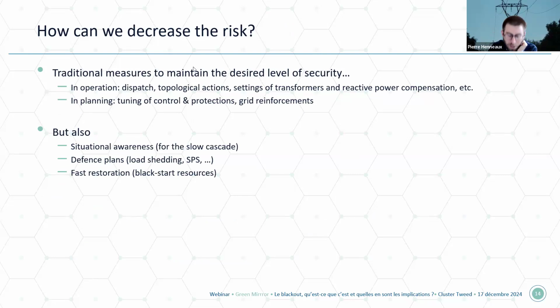We can have the analogy with the measures to ensure deterministic N-1 security. So the traditional measures to maintain the desired level of security are, in operation, the dispatch and the use of topological actions. So we can change the dispatch to reduce the overloads after a contingency. We can use topological actions also to avoid overloads. We can set in other ways transformers, reactive power compensation, and so on. We can tune in planning, control, and protection. We can also have grid reinforcement.